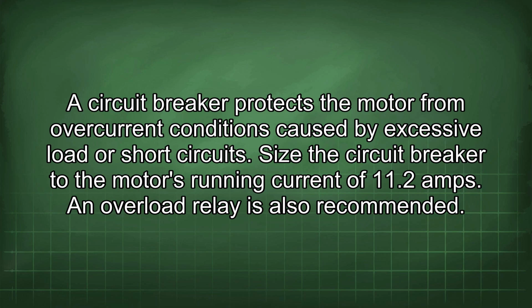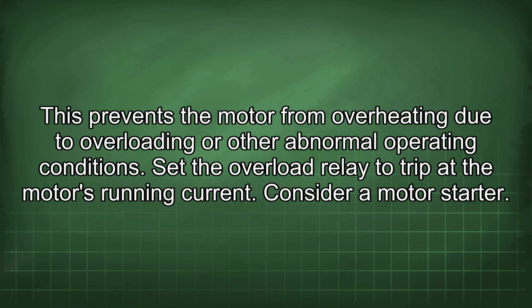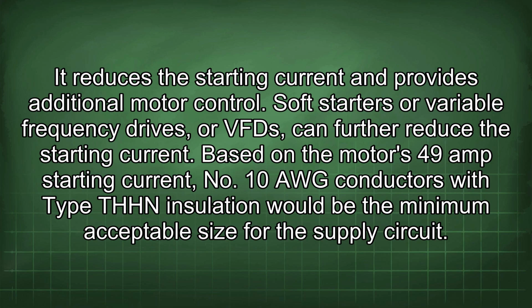Size the circuit breaker to the motor's running current of 11.2 amps. An overload relay is also recommended. This prevents the motor from overheating due to overloading or other abnormal operating conditions. Set the overload relay to trip at the motor's running current. Consider a motor starter. It reduces the starting current and provides additional motor control. Soft starters or variable frequency drives, or VFDs, can further reduce the starting current.